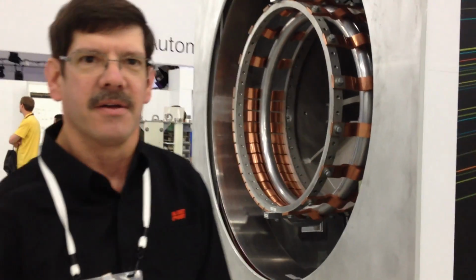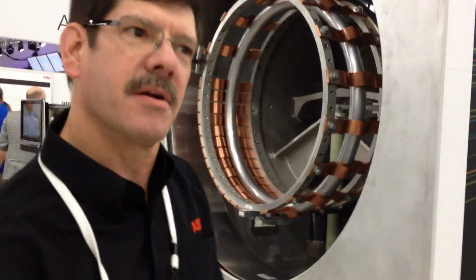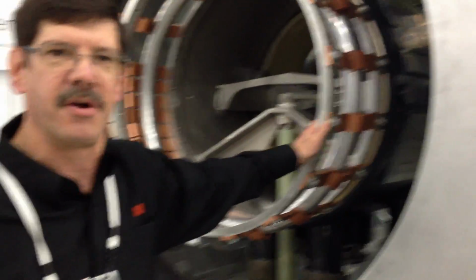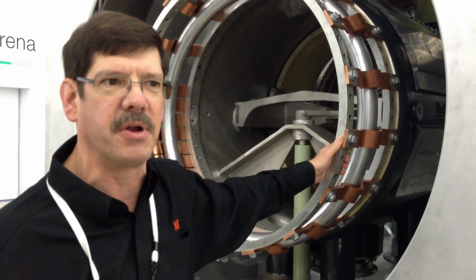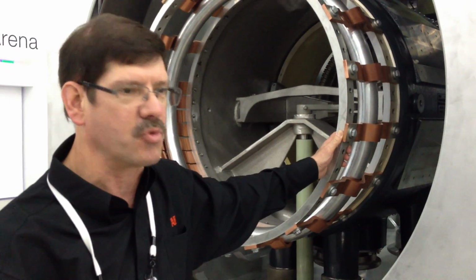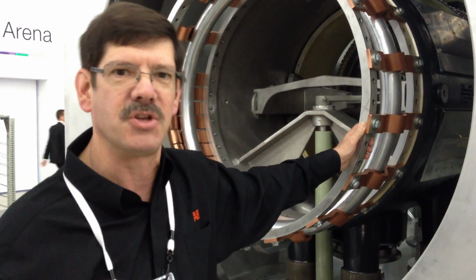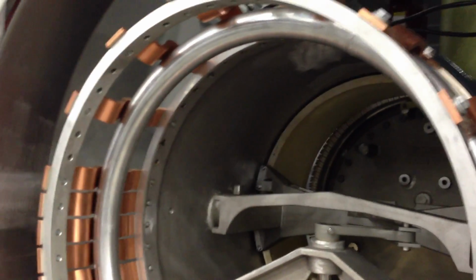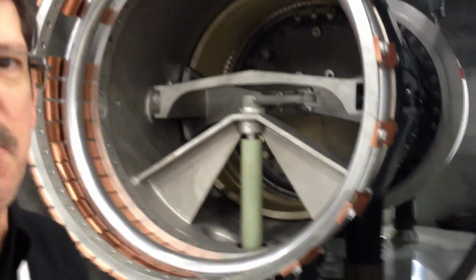So, Lewis, can you show us what's inside this thing? Absolutely. What we have here is what's called a generator circuit breaker, a component that is typically installed between the generator and the main GSU transformer. Its purpose is to isolate the generator from the GSU transformer. It allows for an isolation or break point, and it interrupts current.